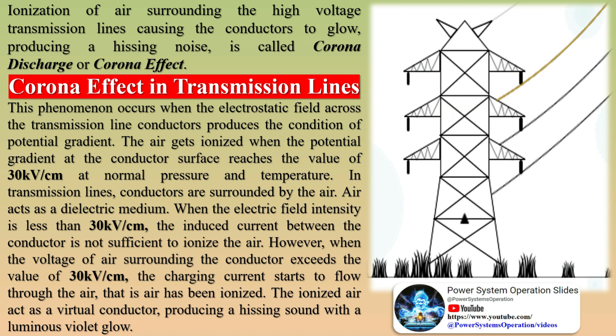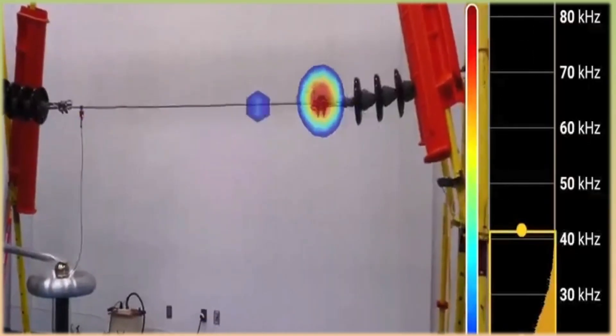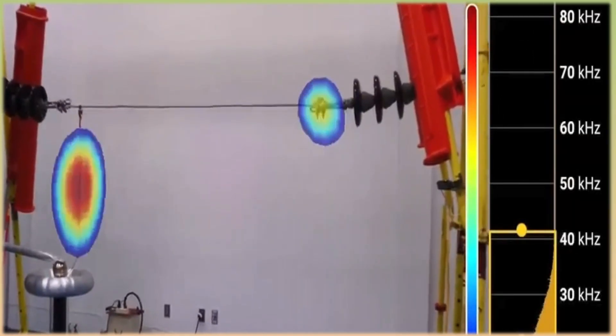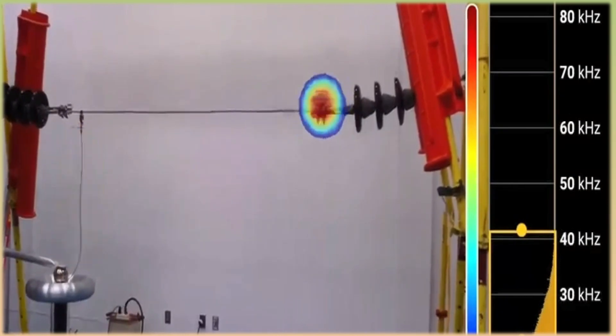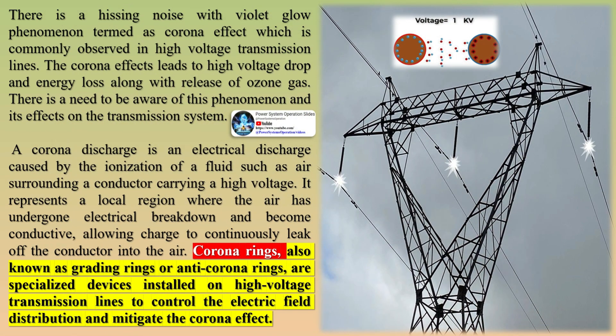In transmission lines, conductors are surrounded by air, which acts as a dielectric medium. When the electric field intensity is less than 30 kV/cm, the induced current between the conductors is not sufficient to ionize the air. However, when the voltage of air surrounding the conductor exceeds 30 kV/cm, the charging current starts to flow through the air — that is, the air has been ionized.